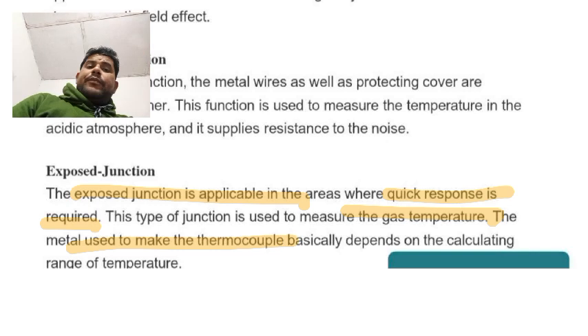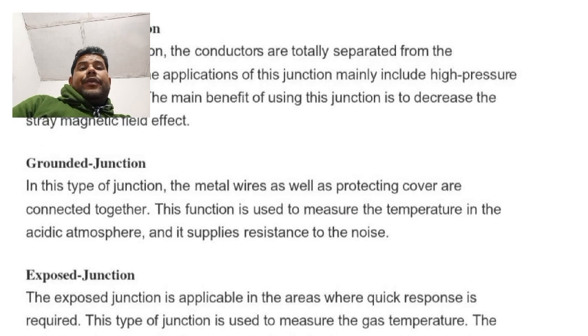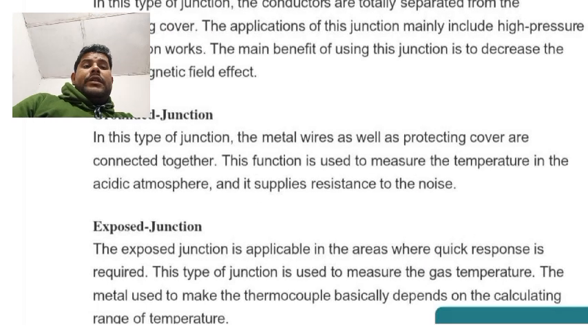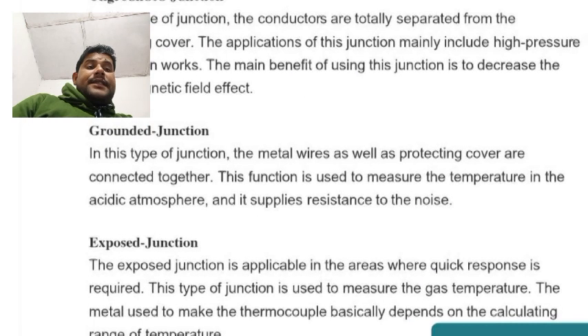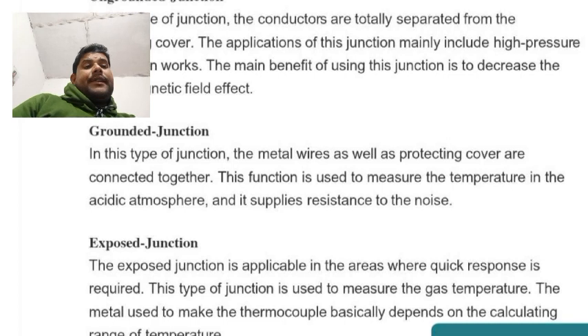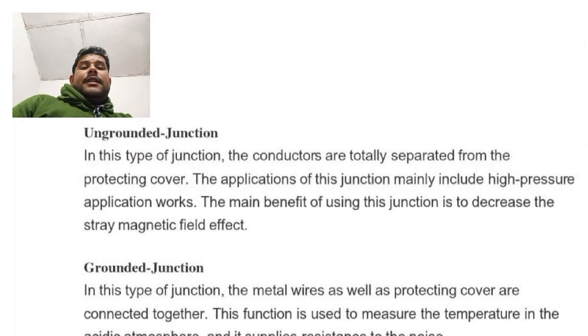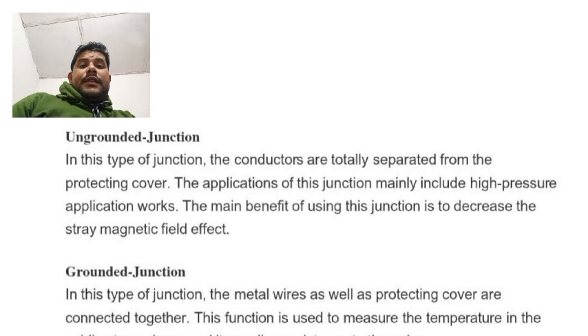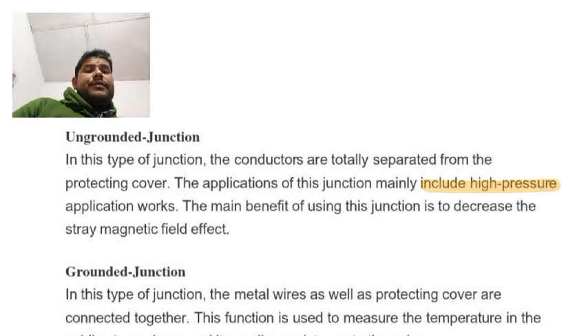For measurement of gas temperature, we need an exposed junction type thermocouple. For grounded type, it is used to measure temperatures in acidic atmospheric conditions. This is an ungrounded junction type, generally used for high pressure applications.